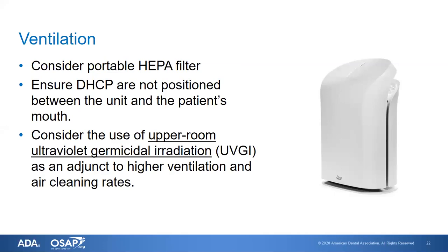One of the other new recommendations is considering the use of what's called upper-room ultraviolet germicidal irradiation, or UVGI. This involves ultraviolet lights installed in the upper part of the room near the ventilation, because UV at a certain range will inactivate microorganisms. This would be an adjunct to your existing ventilation system — as air is drawn through that area, it would also inactivate certain numbers of microorganisms.